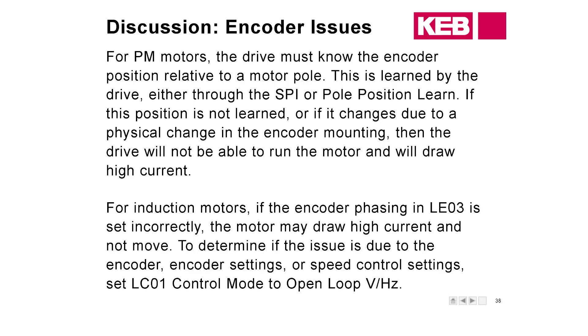We're getting a command speed — encoder issues. Some common problems with encoders: loose wire connections, and the pulse number that needs to be entered correctly into the drive. For TTL incremental encoders on induction geared machines, you need to make sure you're wired correctly to the terminal strip on the drive, and that you have a voltage differential between your channel pairs — between your A and B channels. If you don't have that differential, you should have an error that pops up, and you won't be able to run in closed-loop operation.